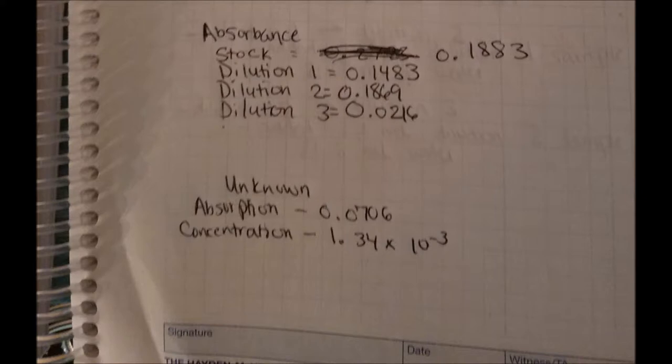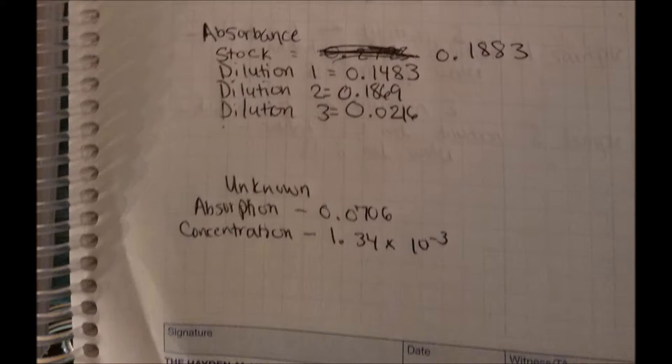The computer automatically saves your data. It reveals the linear relationship between absorption and concentration. Therefore, if you don't zero the machine with a blank in the beginning, the absorption values will be incorrect because the water is not negated in the dilution, and once you graph, the linear relationship will not be reflected.